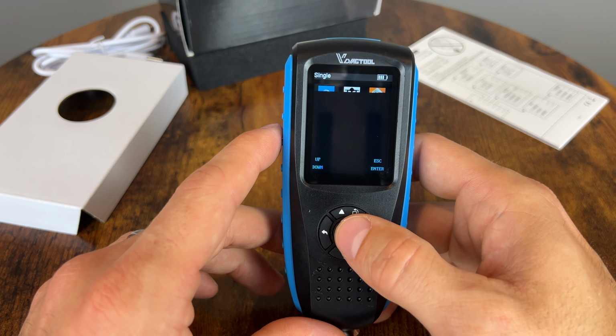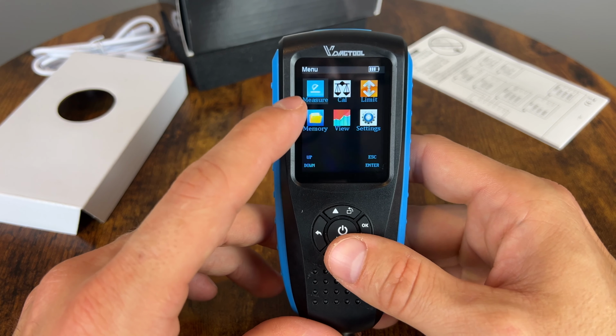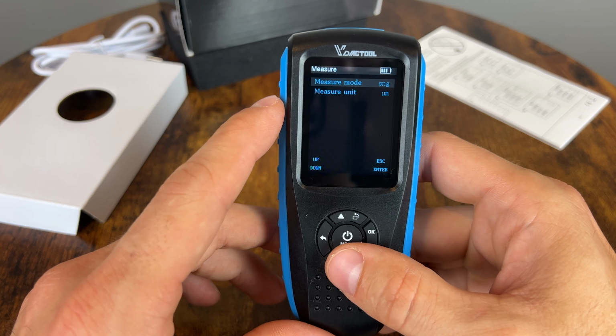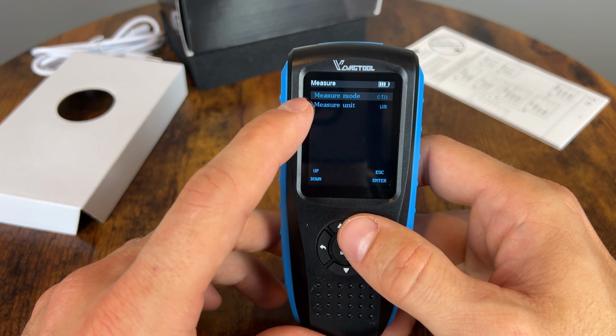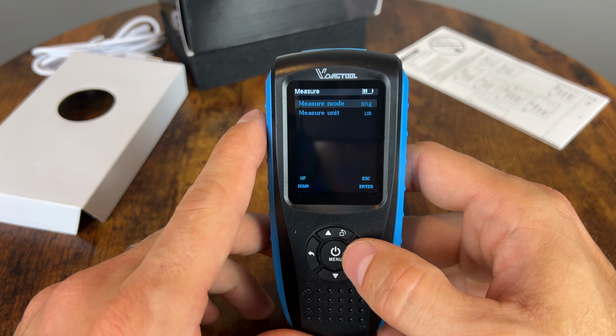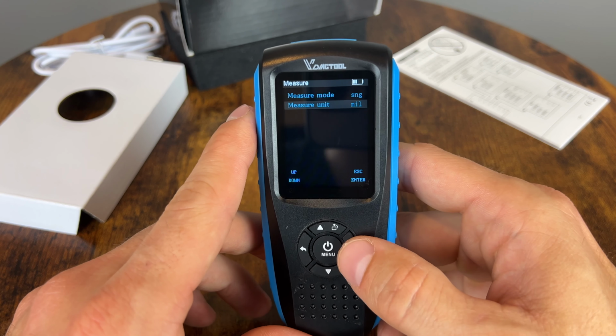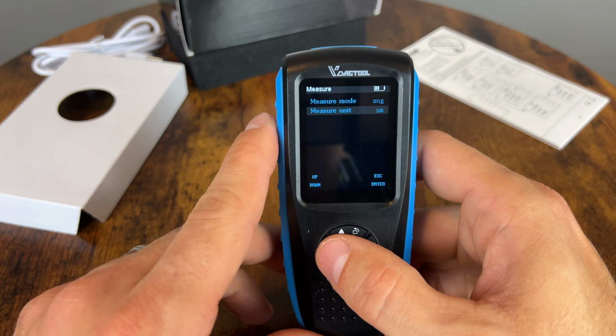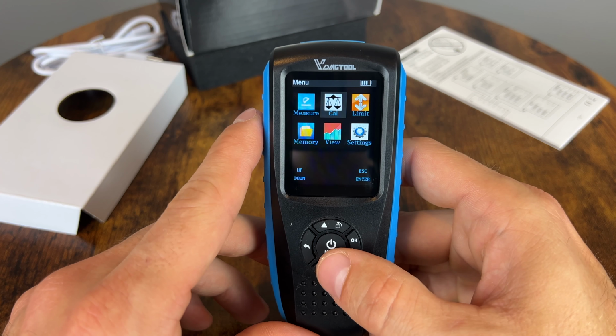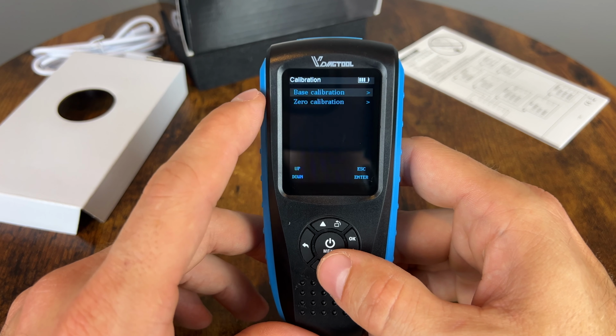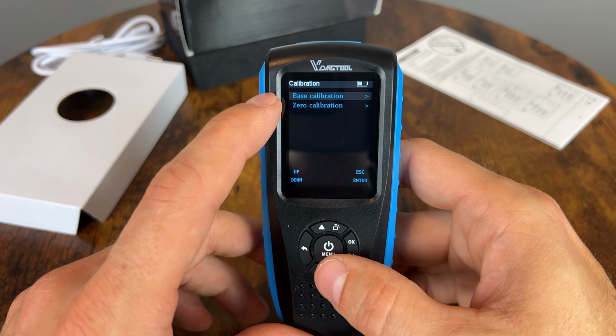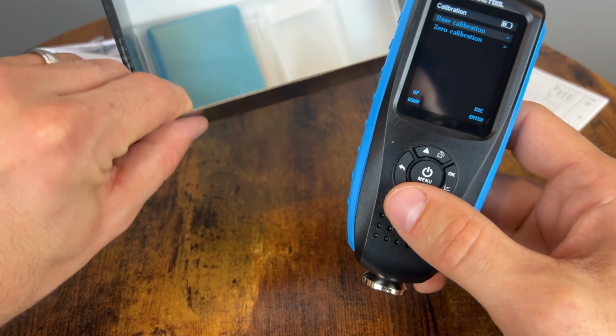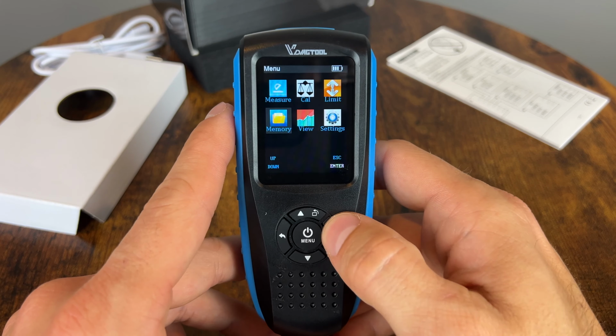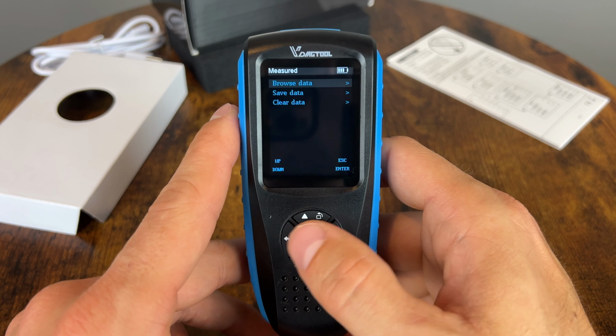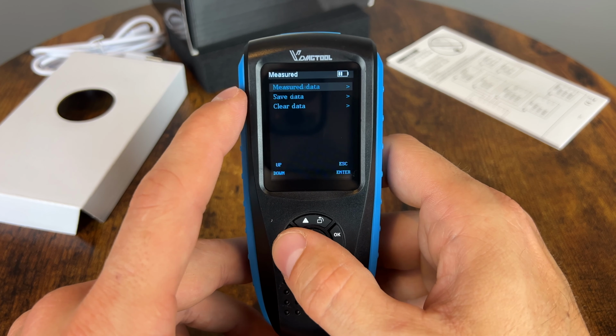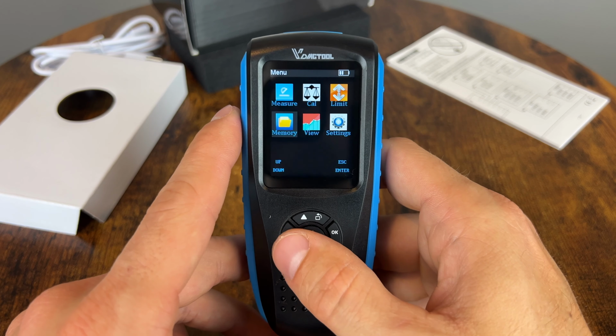But let's go quickly into the menu and see what it offers here. So here in the measure menu, we can switch between singular or continuous, as you can see right there. And we can switch the units between microns and mils. I like microns, like I said, it's more precise. Of course, we can go to cal, and this is going to do the calibration for you. So base calibration or zero calibration, using those items right there. Memory, so you can go back into the memory and see the data that you have done before, if you were to save it. I haven't saved mine.